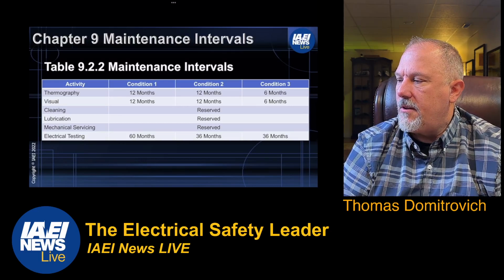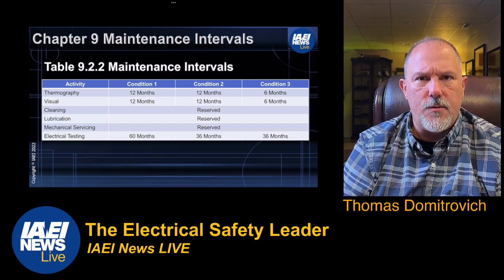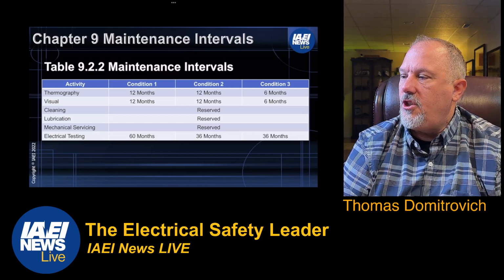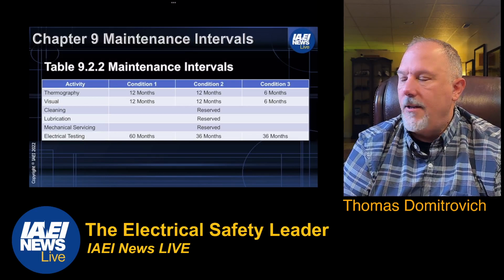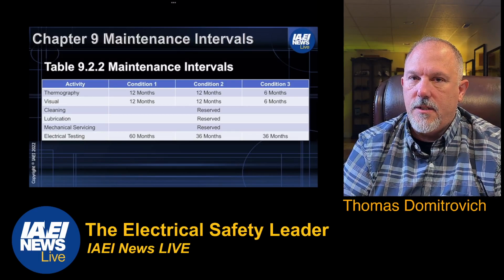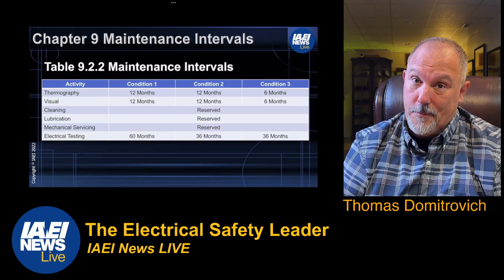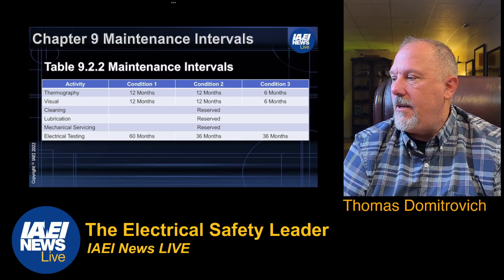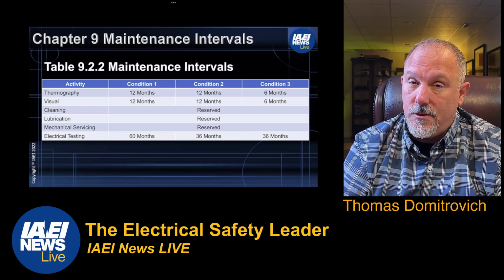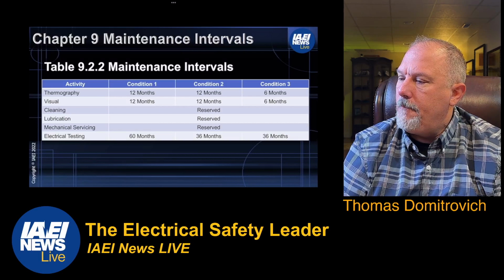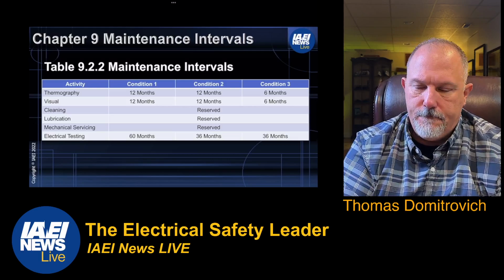I'm surprised condition 3 is the same as condition 2, because as you move from condition 1 to 2 to 3—1 being like new equipment, 2 being a bit beat up, and 3 meaning we've got some issues—you'd expect a difference. But electrical testing is still every 36 months, every 3 years, for condition 3.